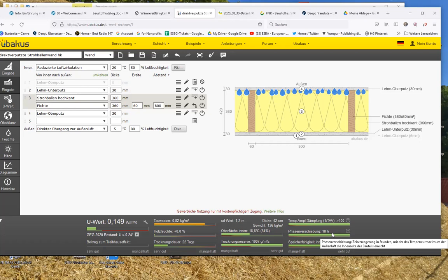That's a really good question. I have the same rule which I learned, that 12 is good, but with these big densities of materials we get to very large values. I even had a construction of 24 hours. Usually 24 hours means that if the next day is a cold, cloudy day, the temperature is still in the right range. But it could also be that you have a warm day and then again a warm day, and then it would theoretically accumulate.